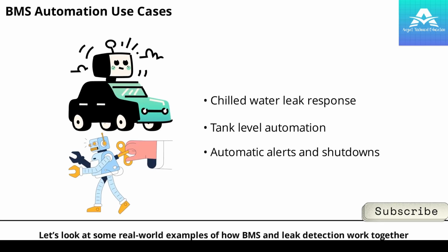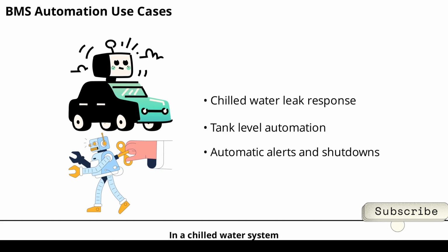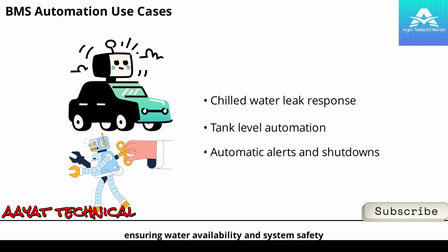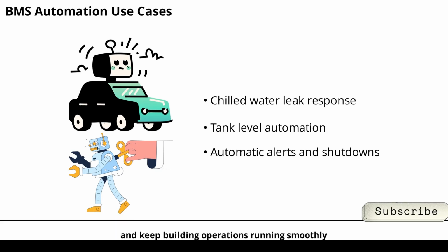Let's look at some real-world examples of how BMS and leak detection work together. In a chilled water system, if a leak is detected, the BMS can immediately alert the operator and automatically shut down the chilled water pump in the affected zone, preventing further damage. For water tanks, ultrasonic sensors monitor levels, and the BMS controls refill valves as needed. If levels fall too low or rise too high for a set period, alarms are triggered, ensuring water availability and system safety. These automated responses save time, reduce risk, and keep building operations running smoothly.